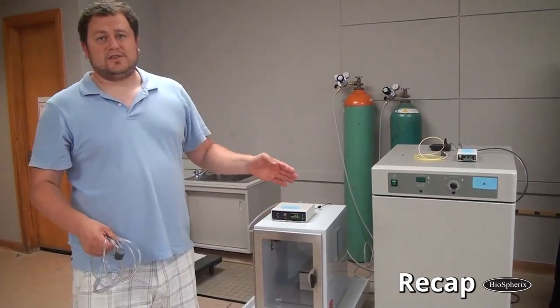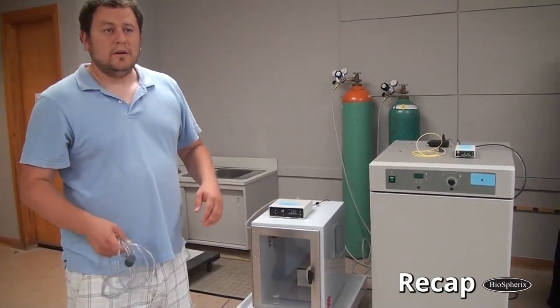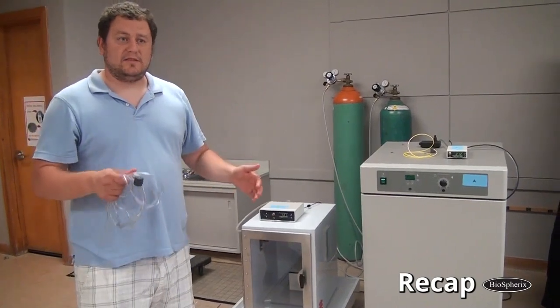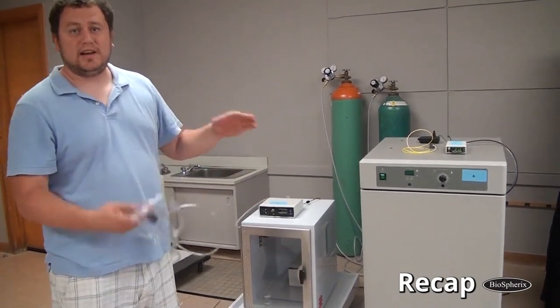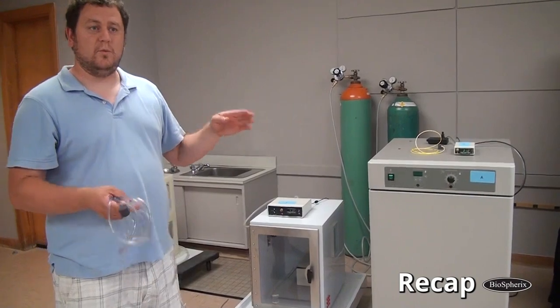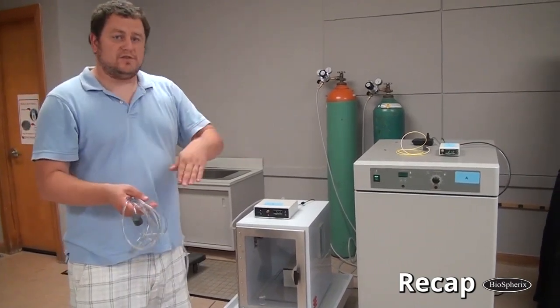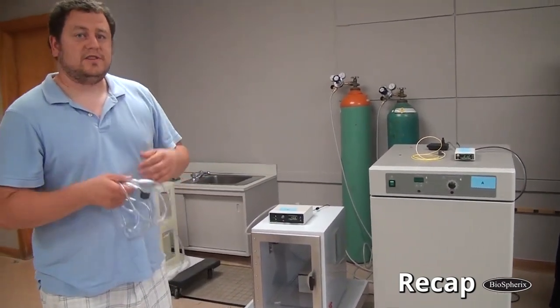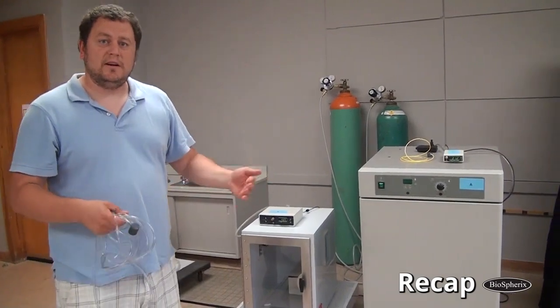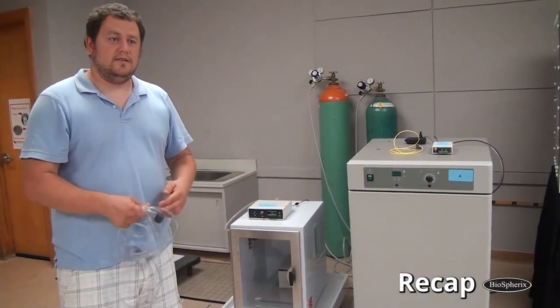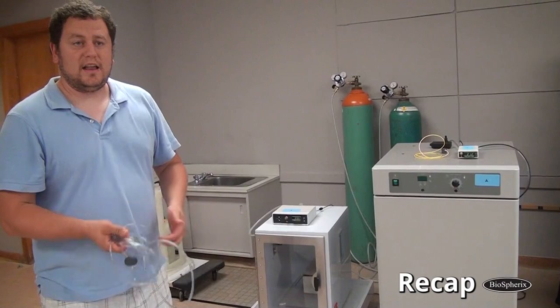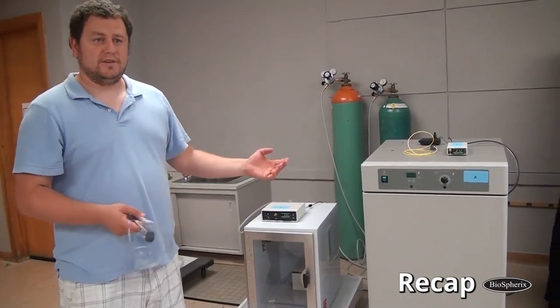sensor usually starts around minus 1.2. Every sensor is different, but that gives you a good idea. And you're going to have a setup sheet with your controller that shows you what it starts at. It might drift a little bit from there, but if you ever see a big change in that number, that's an indicator that either the technique you're using to calibrate might be off, or there's something off with the sensor.